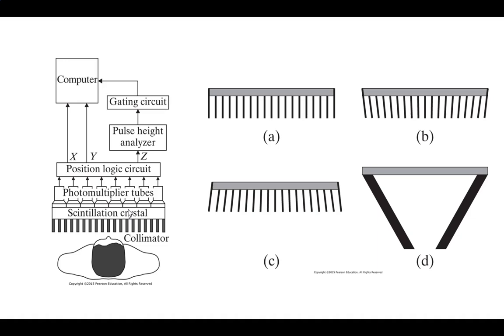In essence, the Compton scattering is actually going to be handled by the pulse height analyzer. Usually you get a curve that looks like this. This is your Compton plateau, and that's the Compton drop-off. Here's your actual pulse, and we'll only let through things at that energy, since we know the energy precisely because of its source. As opposed to our X-ray sources, where the energy was spread across a range, so we know the peak, but we don't know the exact value.